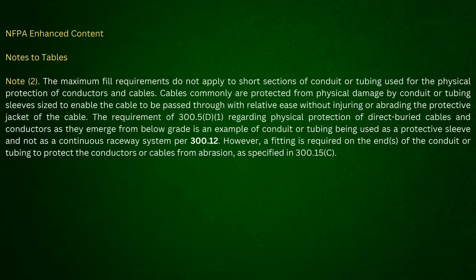Okay, there is one other part here. They say also go look at the requirements of 300.5(D)(1) in regards to physical protection for direct buried cables and conductors as they emerge from below grade, as an example of conduit or tubing being used as a protective sleeve. That goes without saying. Now, if the adjustment factors apply, if I go look at 310.15(C)(1), it talks about more than 3 current carrying conductors, and it tells you that the ampacity of each one of those conductors is permitted to be reduced. And this is where you have the number of current carrying conductors in a raceway or cable exceeding 3. Okay? Now, if I'm looking at a sleeve that's put on there, that is not a raceway. Yeah. It's telling you it's a sleeve.